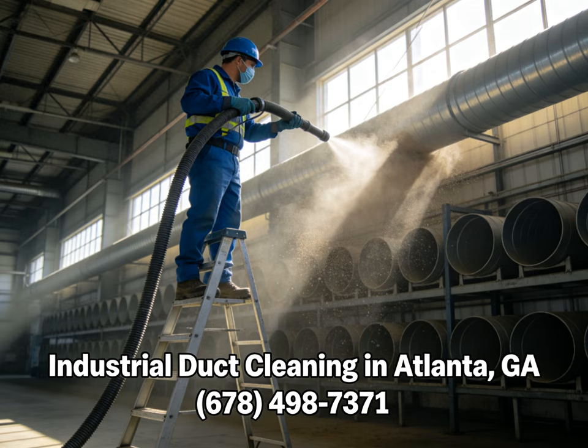It gets much worse when you factor in the affinity laws of fluid dynamics, because the relationship between airflow and energy consumption isn't a straight line, it's exponential. A seemingly tiny drop in airflow, say a 10% restriction from dust buildup, doesn't just mean a simple 10% increase in energy use. It can result in a massive exponential spike in power consumption because the motor has to work that much harder to overcome the friction.